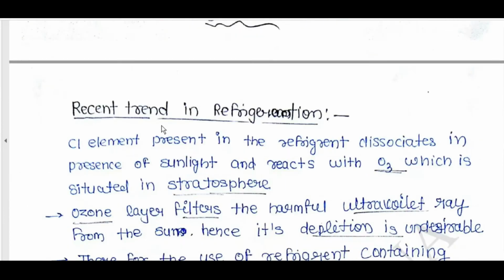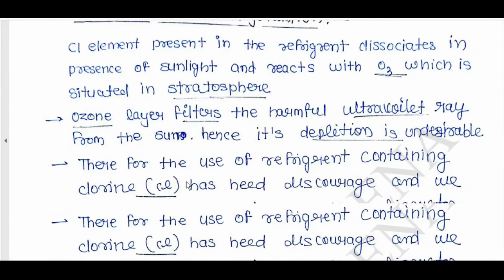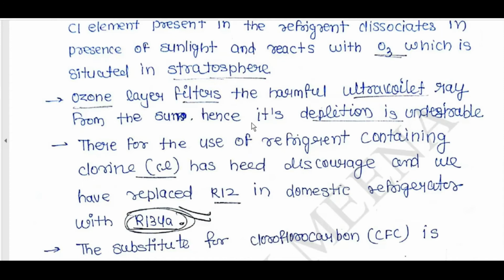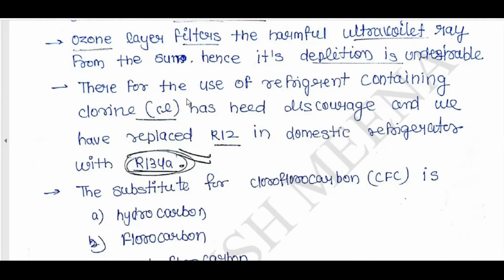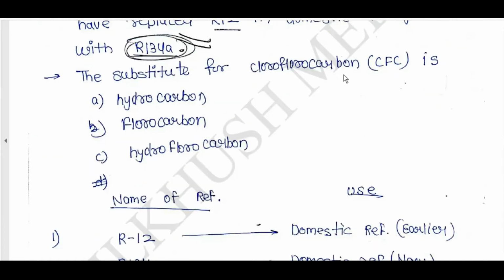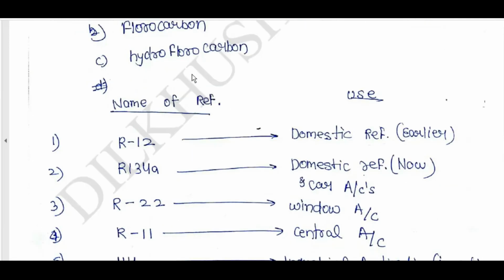Recent trend in refrigeration. The chlorine element present in the refrigerant dissociates in presence of sunlight and reacts with O3, ozone, which is situated in the stratosphere. The ozone layer filters the harmful ultraviolet rays from the sun, hence its depletion is undesirable. Therefore, the use of refrigerants containing chlorine has been discouraged, and we have replaced R12 in domestic refrigerators with R134A. The substitute for chlorofluorocarbon, CFC, is hydrofluorocarbon.